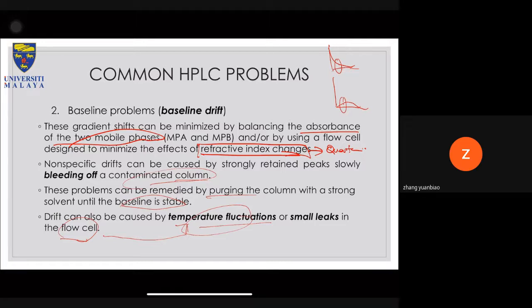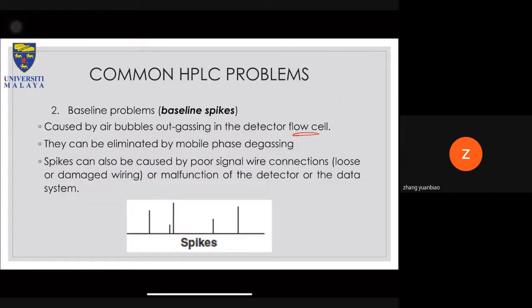All right, spike problems. So it is normally caused by air bubbles bubbling out or gassing in the detector flow cell. So this is what I mentioned previously. They can be eliminated by mobile phase degassing or purging. Spikes can also be caused by poor signal wire connection, or loose or damaged data wiring, and malfunction of the detector or the data system. So this is what happened to me a long time ago.